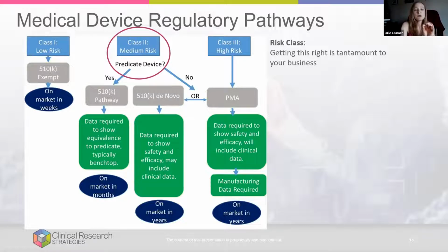But if you are shown to be a class 3, the other possibility then is your PMA. So you can be pushed to a PMA if the reason why there's no predicate device is that you're actually a higher risk. And so then you go to a pre-market approval, which requires full clinical data, and oftentimes manufacturing data as well. And you're on the market in years.